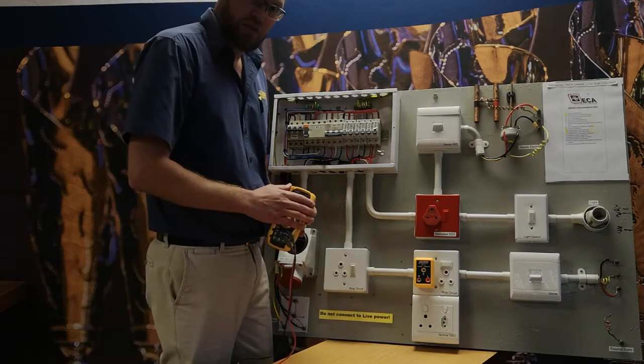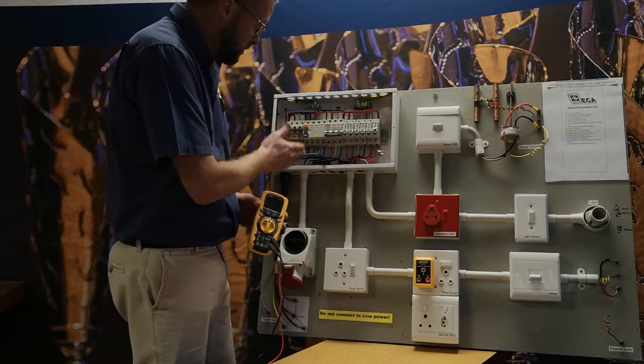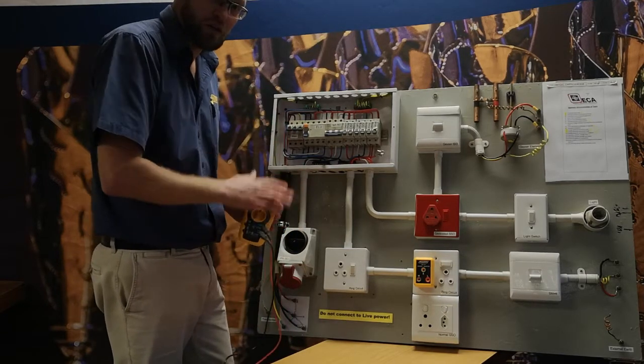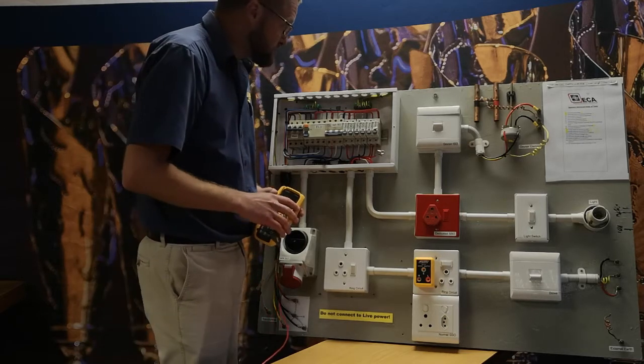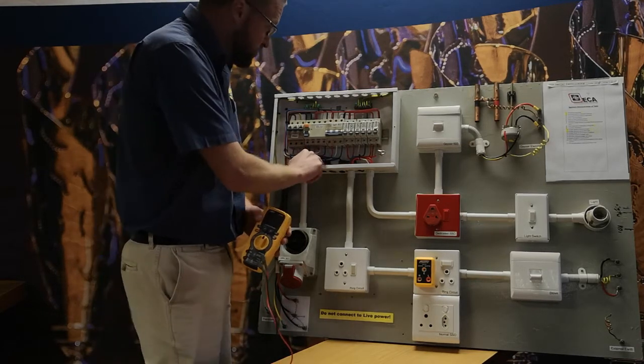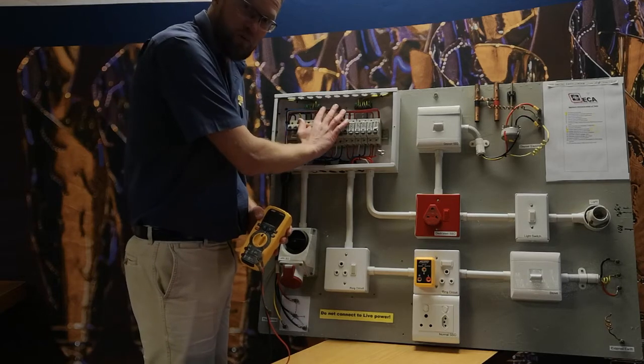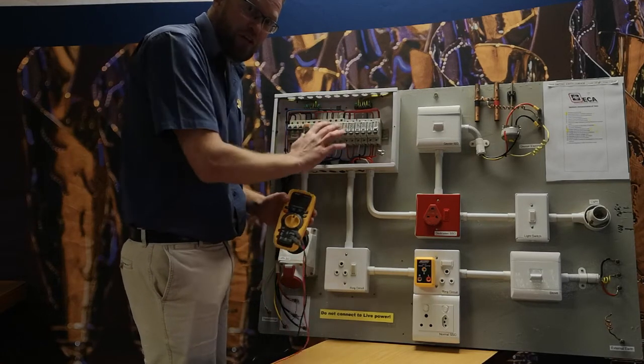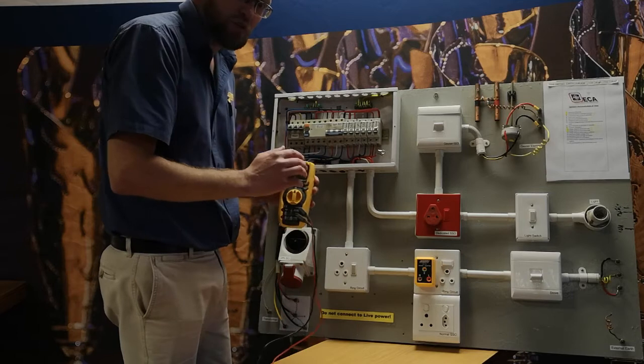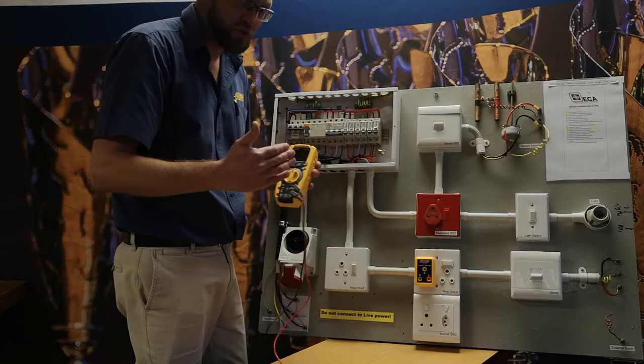The next test is elevated voltage on your incoming main neutral. Most guys make the mistake of testing between your neutral and your earth bar in your main DB. They're both connected to the same point in your installation, so you won't pick up any differentials there or any voltage.